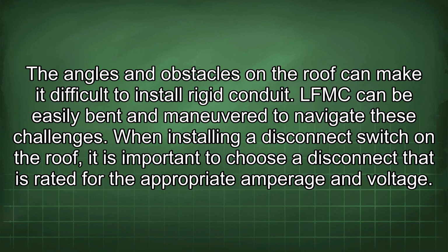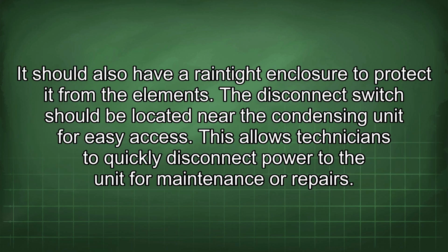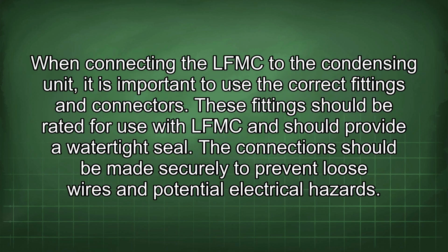When installing a disconnect switch on the roof, it is important to choose a disconnect that is rated for the appropriate amperage and voltage. It should also have a rain-tight enclosure to protect it from the elements. The disconnect switch should be located near the condensing unit for easy access. This allows technicians to quickly disconnect power to the unit for maintenance or repairs. When connecting the LFMC to the condensing unit, it is important to use the correct fittings and connectors. These fittings should be rated for use with LFMC and should provide a watertight seal. The connection should be made securely to prevent loose wires and potential electrical hazards.